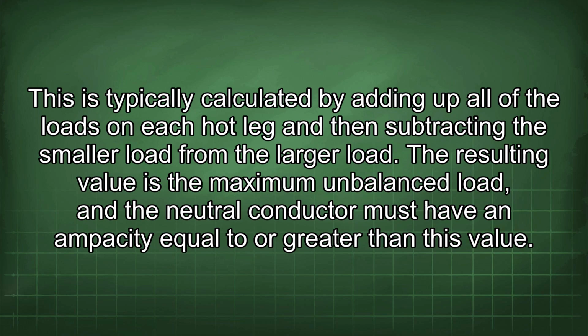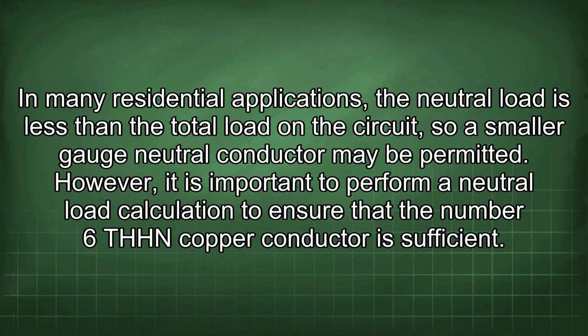The resulting value is the maximum unbalanced load, and the neutral conductor must have an ampacity equal to or greater than this value. In many residential applications, the neutral load is less than the total load on the circuit, so a smaller gauge neutral conductor may be permitted.